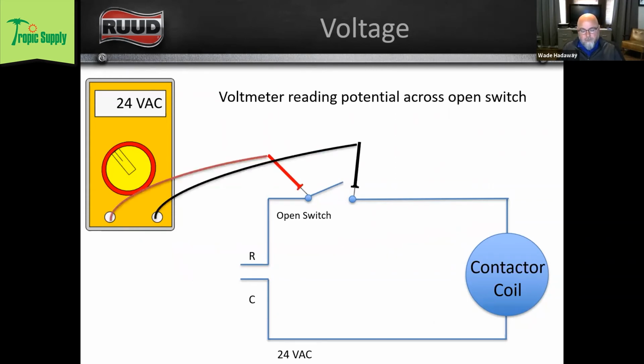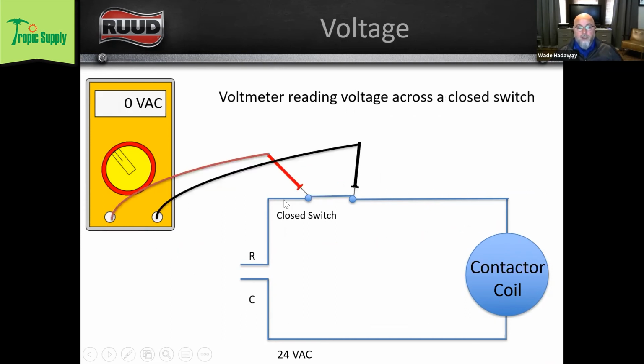And so this is a very common misconception and a common mistake that people make when they're using their meter. When you check voltage across an open switch, if you're getting voltage there, that's telling you that the switch is open, right? And we're reading just 24 volt electrical potential, which is sitting right here. Once we close that switch, and the electrons are flowing through the switch, we shouldn't read any voltage because we don't have a load there, and we shouldn't see a voltage drop across that switch.